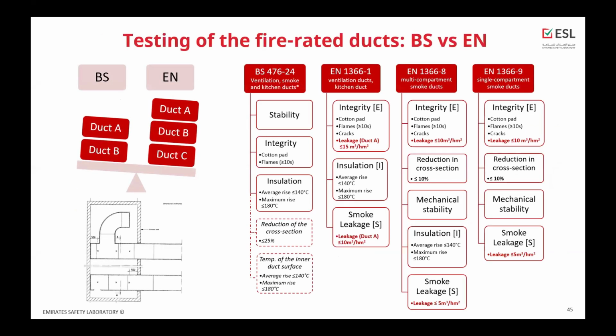So if we compare these two families of test methods, BS and EN, you can see that BS refers to two types of duct, duct A and duct B, whereas EN introduces a third type of duct, duct C. In terms of criteria, BS is not defining criteria for leakage. However, BS 476 part 24 mentions in the text that it may be measured, but it is not mandatory, and there is no criteria established for such measurement.